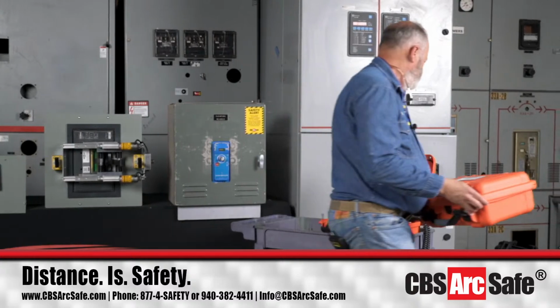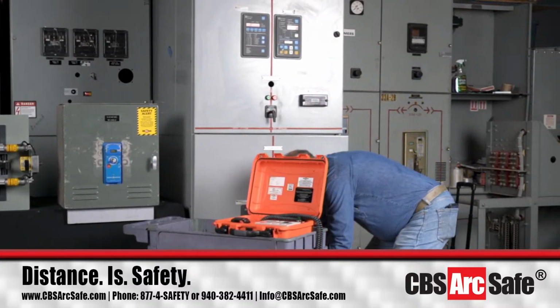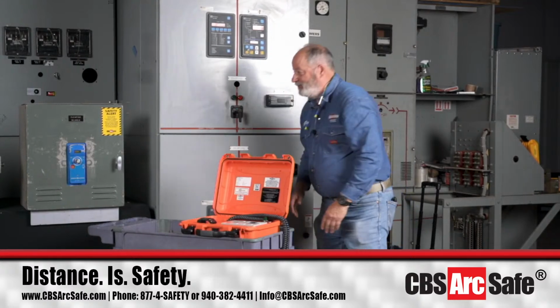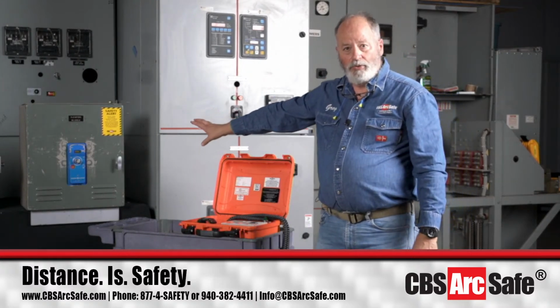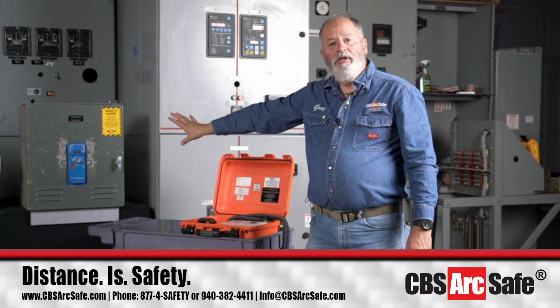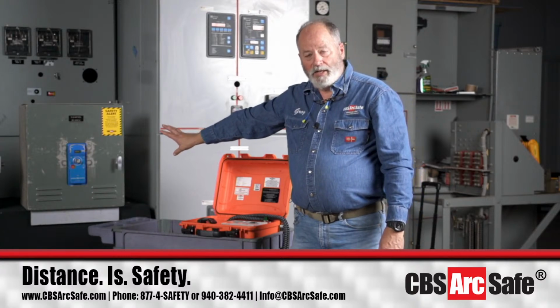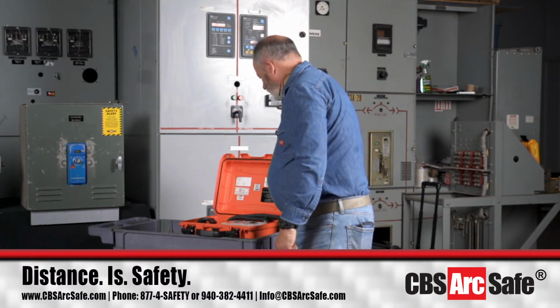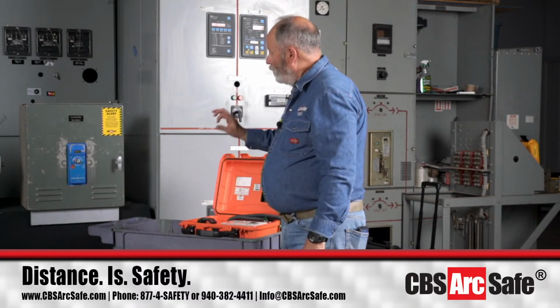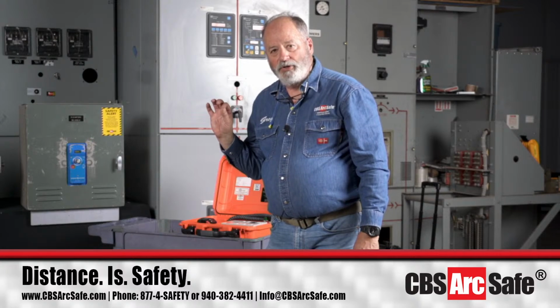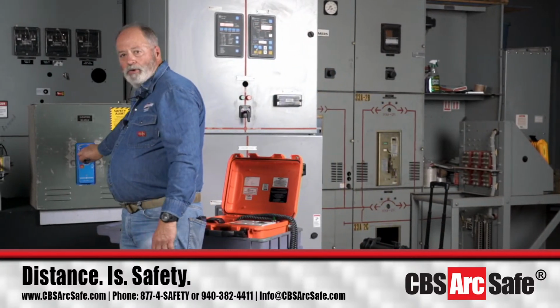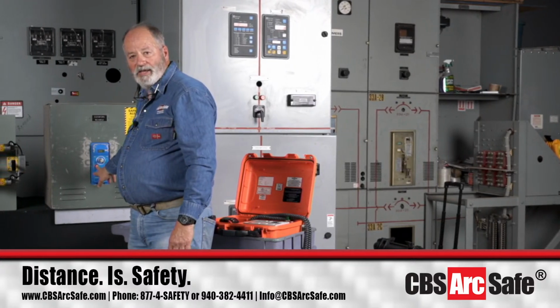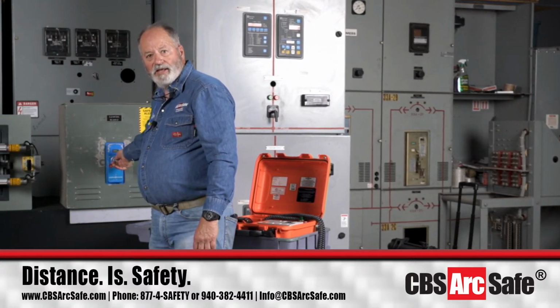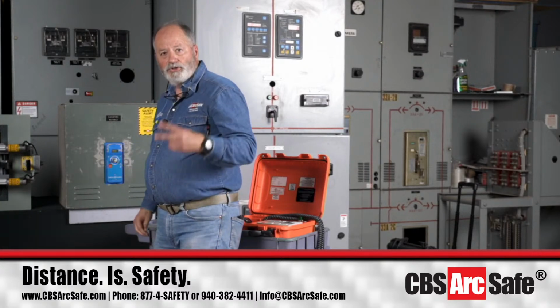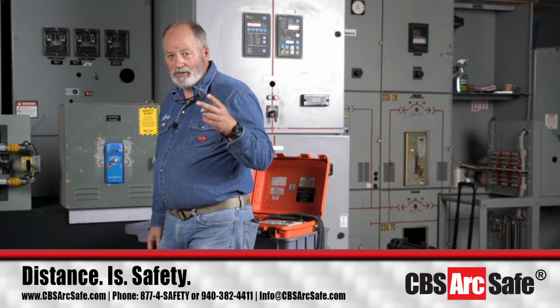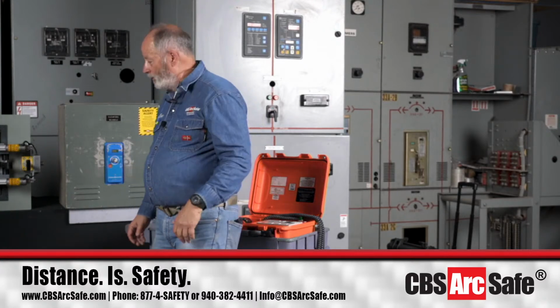The next one we're going to use: General Electric made the AK series of breakers starting back in the 1950s, and this is from an AK2 series breaker. We have the RS2, which can install and remove this circuit breaker and its bigger brother, the AK2, and operate it. For the General Electric series of circuit breakers, because the handle is right there, you can't get to the trip button with the handle in place, so for our actuators you have to take that gray plastic handle off. There are two Allen screws, set screws inside the handle, you have to remove to get it off to be able to put the actuator on.